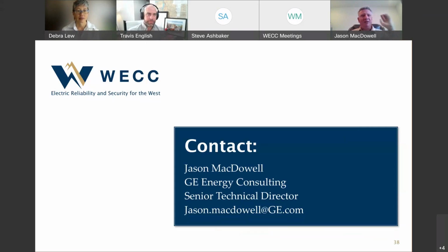Inertia is fundamentally the coupling of the synchronizing torque and the rotating mass of synchronous machines together with the energy injection given by inverter-based resources to arrest that initial decline. So the name of the game is how all resources work together during a system event to arrest that initial decline, providing the appropriate amount of energy and coordinating with later layers of control, primary frequency response, governor response, and eventually balancing the system out.